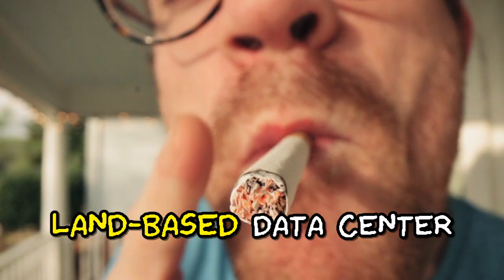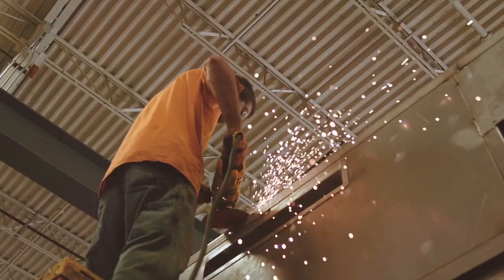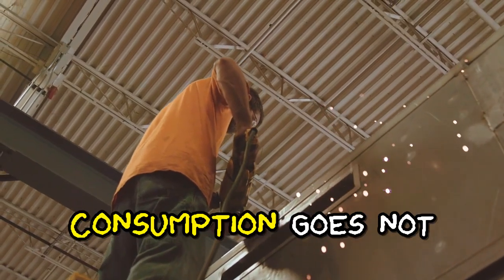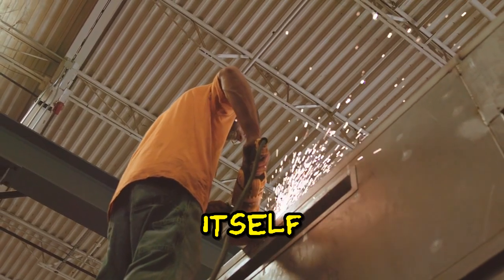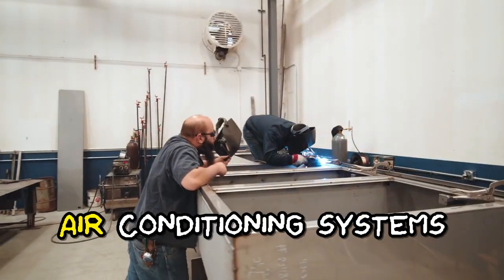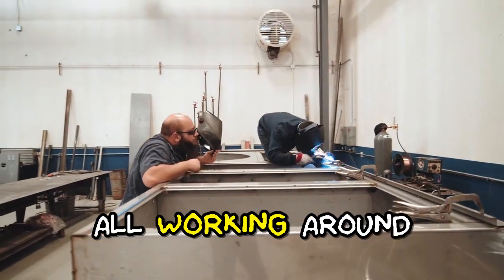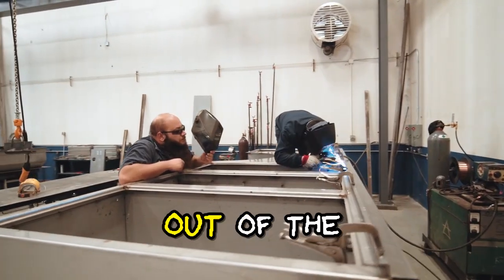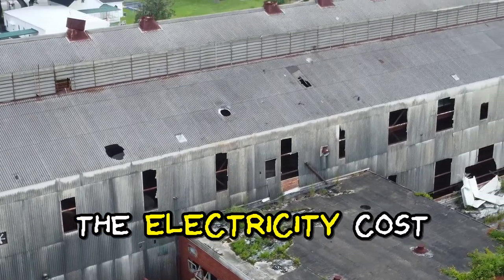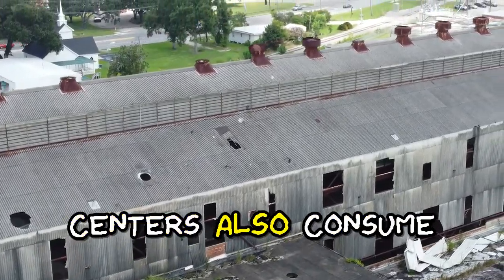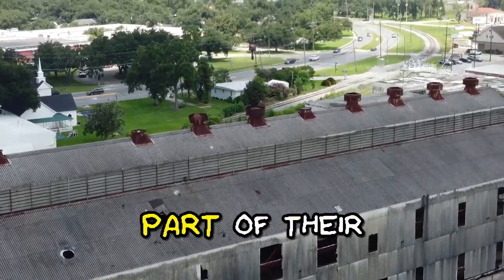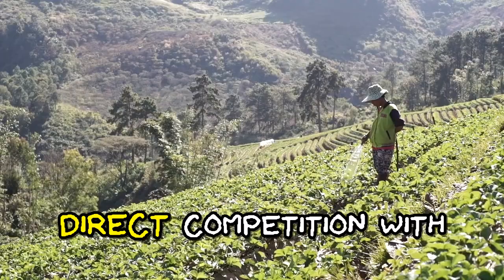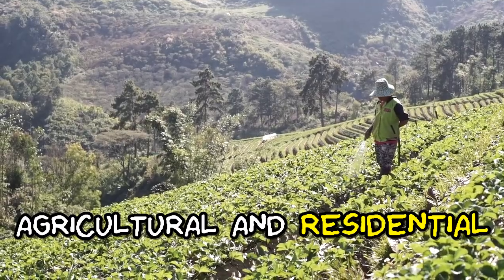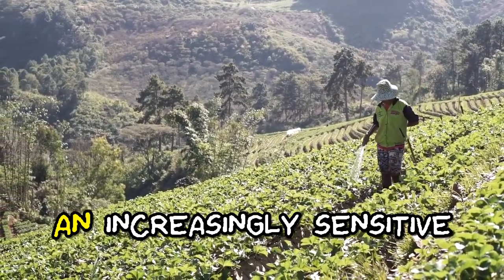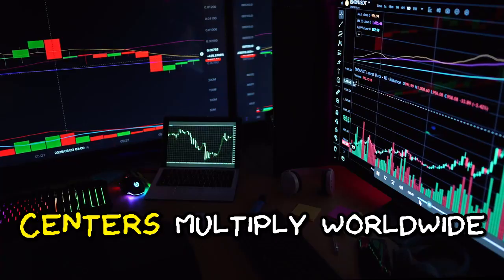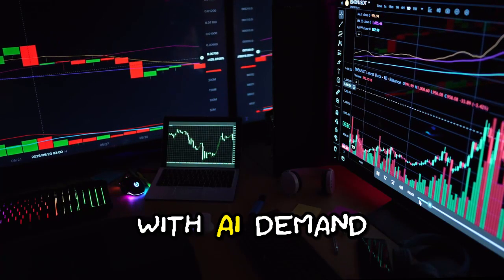In a typical land-based data center, anywhere between 25 and 40% of total electricity consumption goes not toward the computing itself, but toward industrial chillers, air conditioning systems, and pumps, all working around the clock purely to move heat out of the building. On top of the electricity cost, most conventional data centers also consume large amounts of fresh water as part of their cooling process, putting them in direct competition with agricultural and residential water needs in the regions where they operate, an increasingly sensitive issue as data centers multiply worldwide to keep up with AI demand.